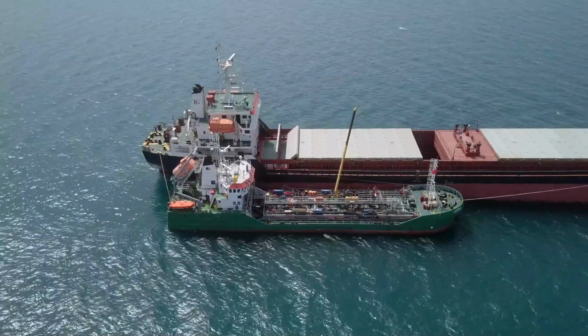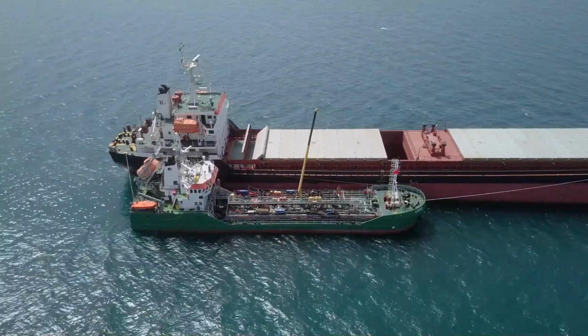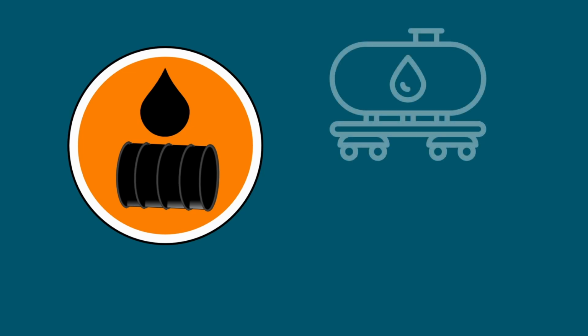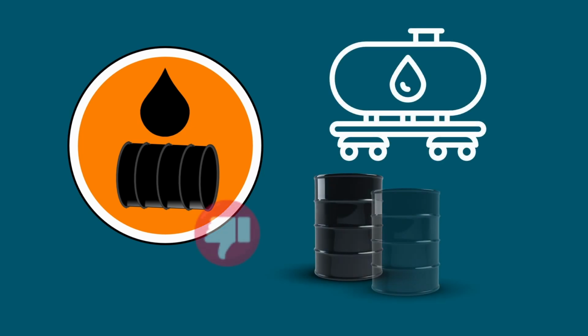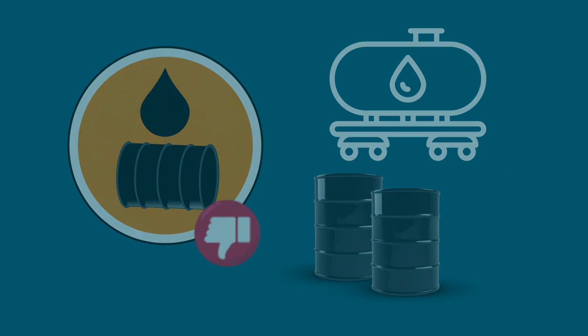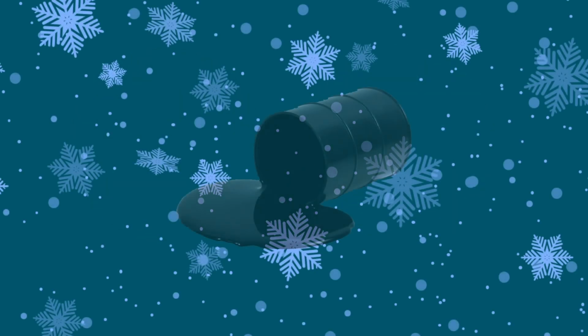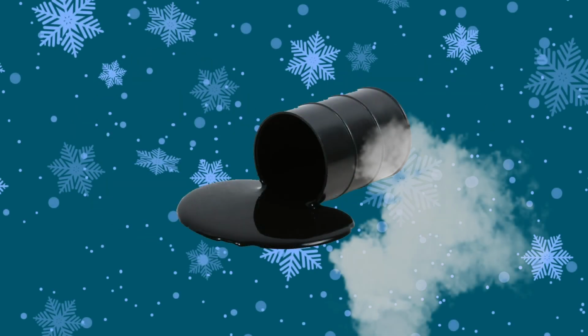marine fuel in tanks. When it comes to fuel oil, the quality of this petroleum product deteriorates during transportation and storage. Oxidation and polymerization reactions occur in fuel oil and make hydrocarbons change into solids and precipitate. In the cold season, fuel oil is heated in railway tanks using hot steam. Furthermore, fuel oil is additionally water cut. In worst-case scenarios, the amount of water in bunker fuel oil may reach 10 to 15%.